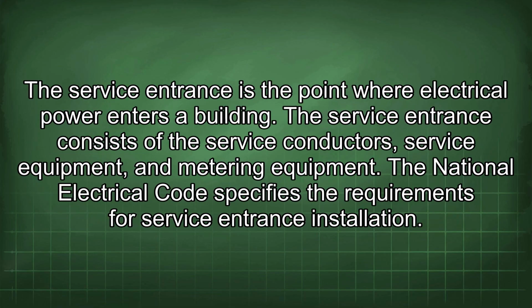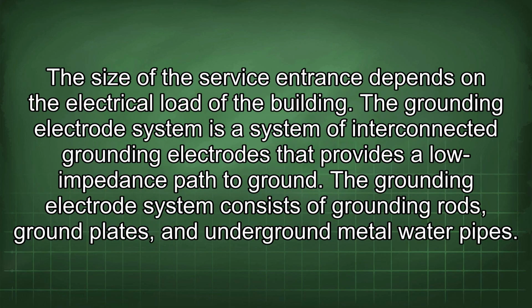The service entrance is the point where electrical power enters a building. The service entrance consists of the service conductors, service equipment, and metering equipment. The National Electrical Code specifies the requirements for service entrance installation. The size of the service entrance depends on the electrical load of the building.